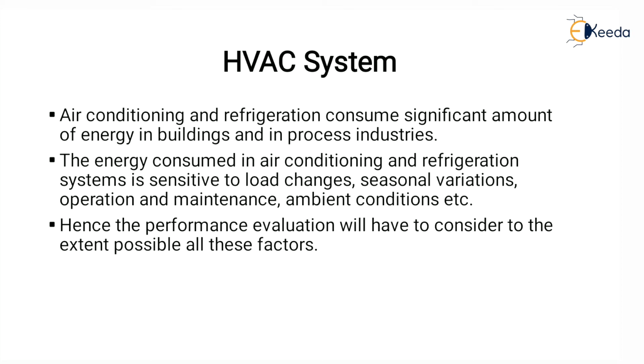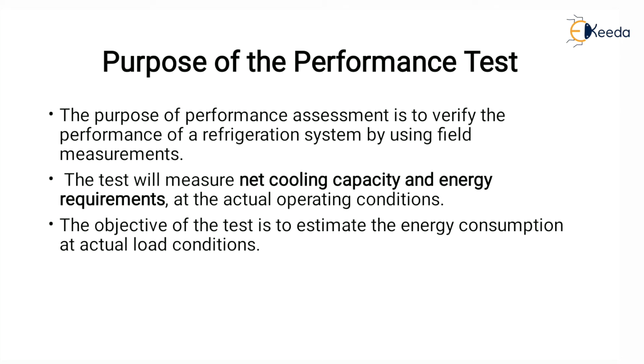Now let us see what is the purpose of performance test. The purpose of performance assessment is to verify the performance of refrigeration system by using field measurement. The test will measure net cooling capacity and the energy requirement at the actual operating condition. The objective of the test is to estimate the energy consumption at the actual load condition. So for this, we require the performance test.